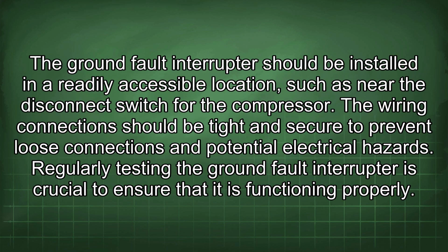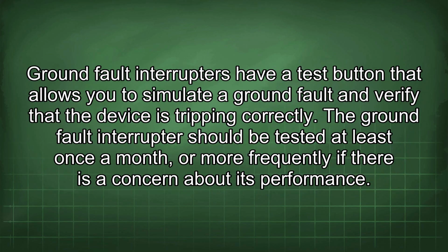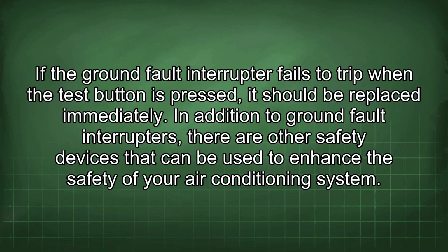The ground fault interrupter should be installed in a readily accessible location, such as near the disconnect switch for the compressor. The wiring connections should be tight and secure to prevent loose connections and potential electrical hazards. Regularly testing the ground fault interrupter is crucial to ensure that it is functioning properly. Ground fault interrupters have a test button that allows you to simulate a ground fault and verify that the device is tripping correctly. The ground fault interrupter should be tested at least once a month or more frequently if there is a concern about its performance. If the ground fault interrupter fails to trip when the test button is pressed, it should be replaced immediately.